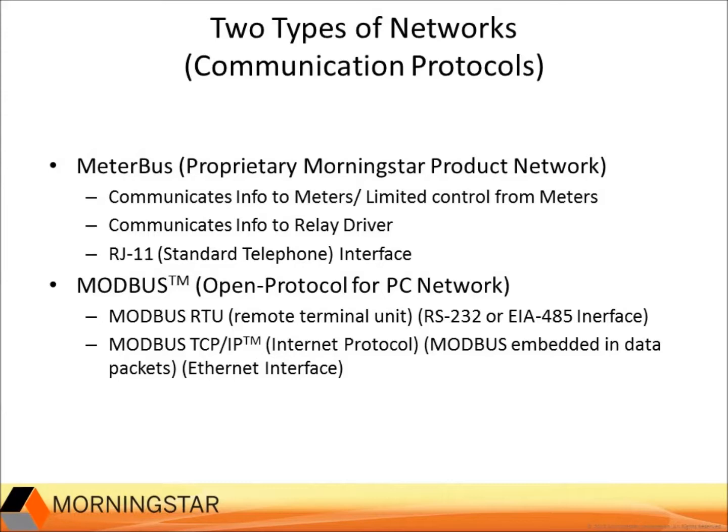Modbus protocol uses RS-232, EIA-485, and Ethernet interfaces for connecting to PCs and other Modbus networking equipment. It is an open and license-free protocol that is widely regarded as the de facto standard in the industrial automation industry. There is an abundance of software and equipment available that directly supports Modbus. RTU is used with serial connections for making a connection to a PC directly or within a Modbus network. Morningstar provides RS-232 and EIA-485 serial interfaces.